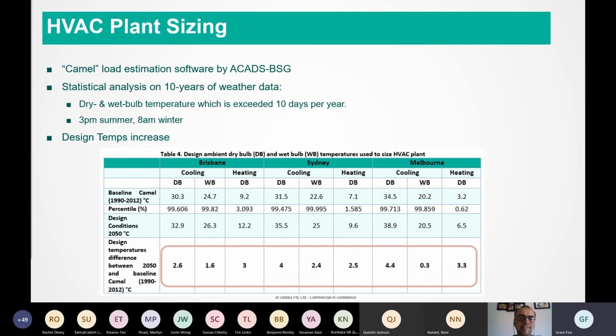But basically, it says that out of 10 years of weather data, so 10 sets of weather files for each location, statistical analysis is then done to establish what the dry bulb and wet bulb temperature is that is exceeded more than 10 days a year. And then for a summer design condition, the 3 p.m. temperature is taken. For a winter design condition, then it's taken at 8 a.m.